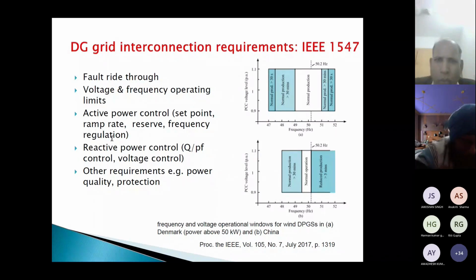For example, now we have photovoltaic systems. Previously, we were operating only at unity power factor, but now we can operate the photovoltaic systems at leading or lagging power factor. It means that these PV systems, through their converters, can supply reactive power. Reactive power supply means that they can help in controlling the voltage. This way, renewable power plants will not be immediately disconnected, but will stay on the grid and help in recovering from the fault condition.